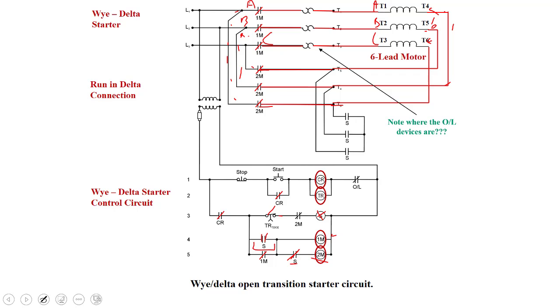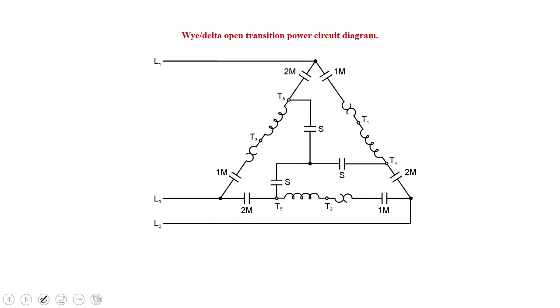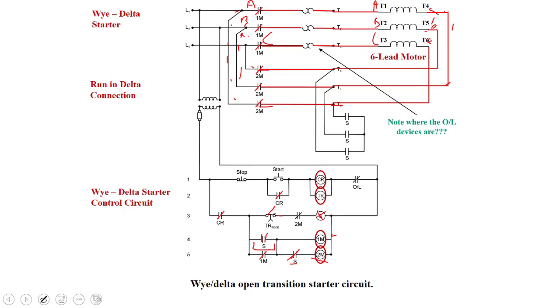Note where the overloads are. They are in the phase. They're not in the line. So when the overloads are in the phase, that means I have to take the FLA of the motor on the motor nameplate and divide that by √3, or times it by 57.7%, and I will get the phase current. Then I can apply my service factor to that, whatever it is in the code book, 1.15 or 1.25, based off the nameplate service factor. So just keep in mind that there's only one set of overloads, and they're going to have to be reduced to the phase current before we apply the service factor.